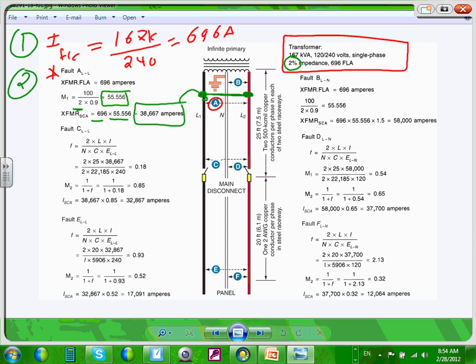They took the full load current with this M1, they call it M1. This is exactly the same as taking the full load current and dividing it by the impedance. The only thing they added is a 10% reduction in the impedance, and that's why they multiplied by 0.9. So your impedance will actually be 0.9 of what's listed, because it could be plus or minus.